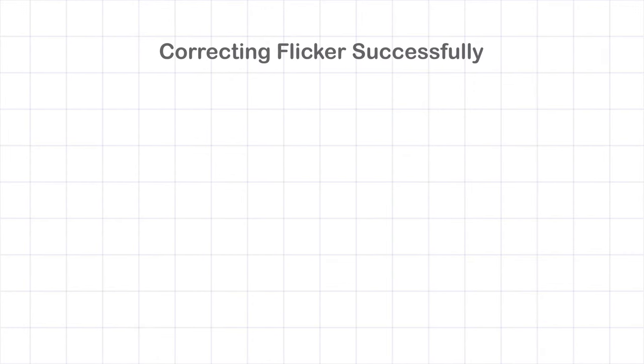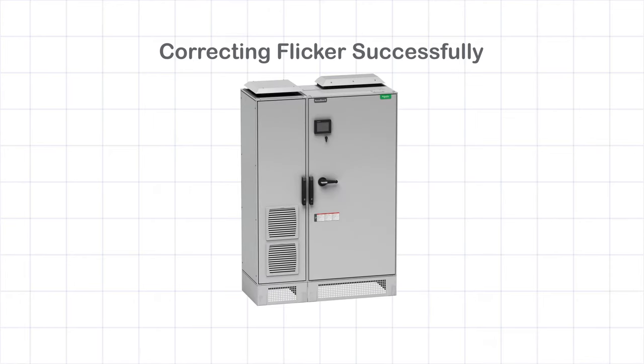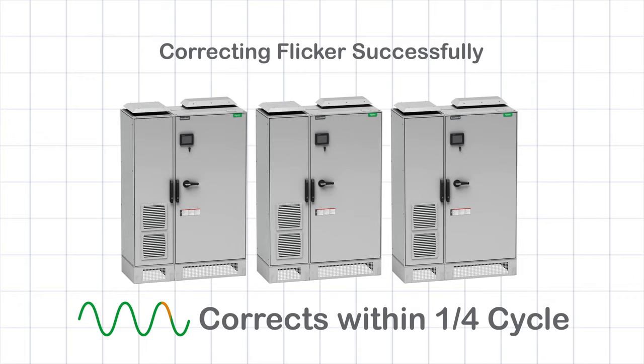To be successful at correcting flicker, you must inject the right amount of reactive power within one electrical cycle. This makes the AccuSine ideal for the job because it's scalable. You install the number of units you need in parallel. And it can inject KVAR within one quarter of a cycle, 4 to 5 milliseconds.